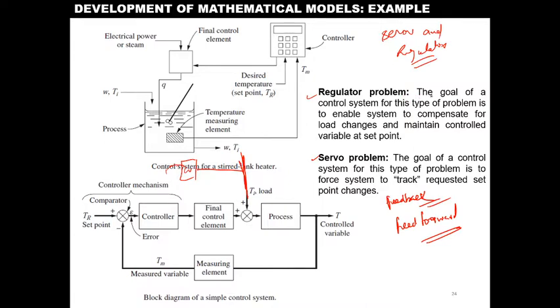In the regulator problem, the goal of the control system is to enable the system to compensate for load changes and maintain the control variable at the set point. The set point is fixed; the load is going to change. In the servo problem, the goal is to track any requested set point change — the set point is going to change. However, the load is fixed and constant. So in the servo problem the load is fixed, and in the regulator problem the load is varying and the set point is fixed.